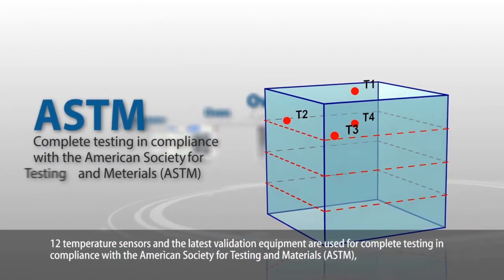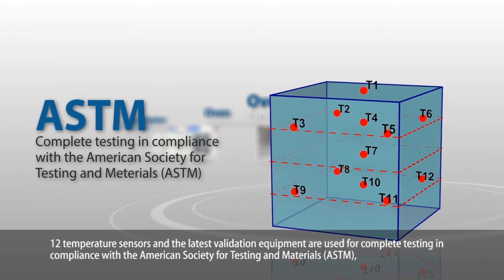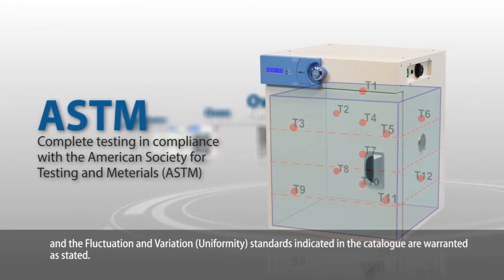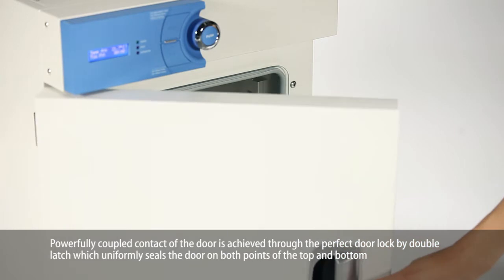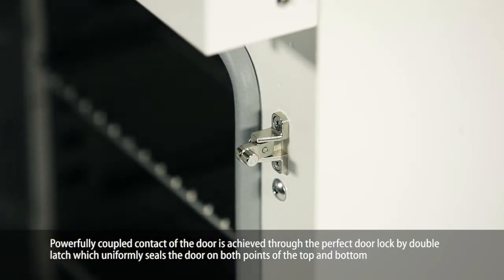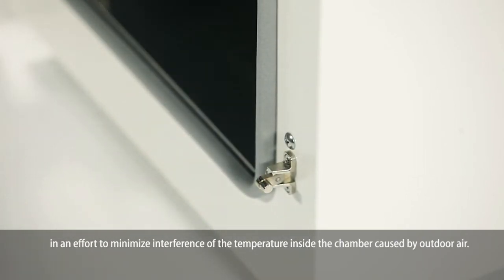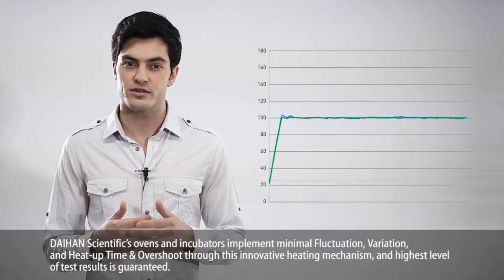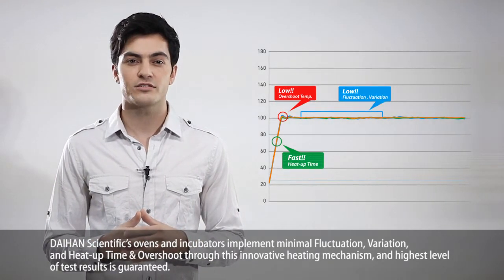12 temperature sensors and the latest validation equipment are used for complete testing in compliance with the American Society for Testing and Materials standards. The fluctuation and variation standards indicated in the catalog are warranted as stated. Powerfully coupled contact of the door is achieved through a perfect door lock by double latch, which uniformly seals the door at both top and bottom points to minimize interference of chamber temperature caused by outdoor air. DAIHAN Scientific's ovens and incubators implement minimal fluctuation, variation, and heat-up time and overshoot through this innovative heating mechanism, and the highest level of test results is guaranteed.